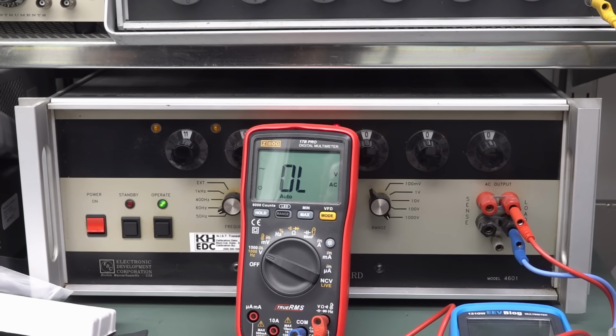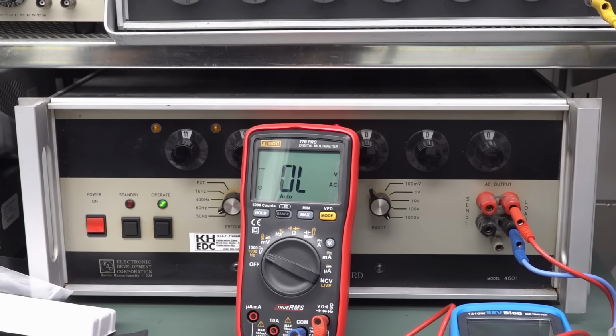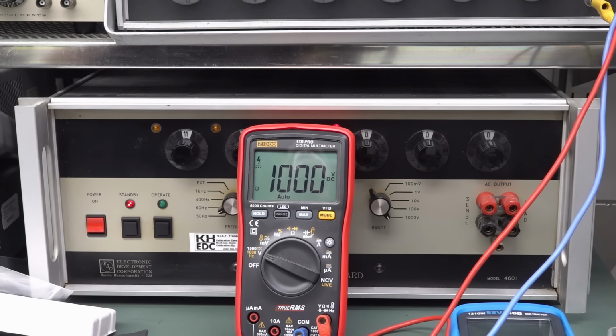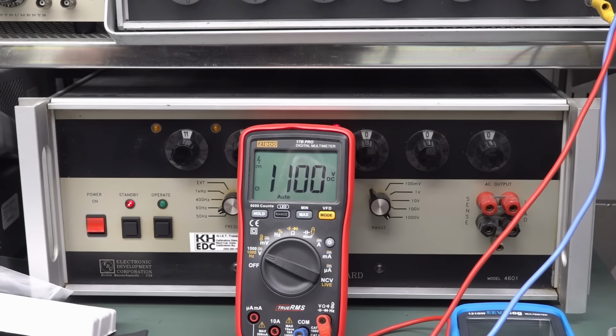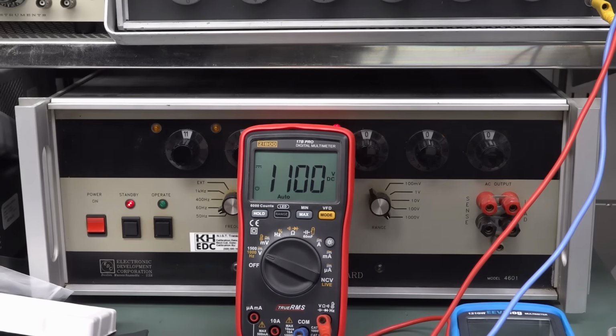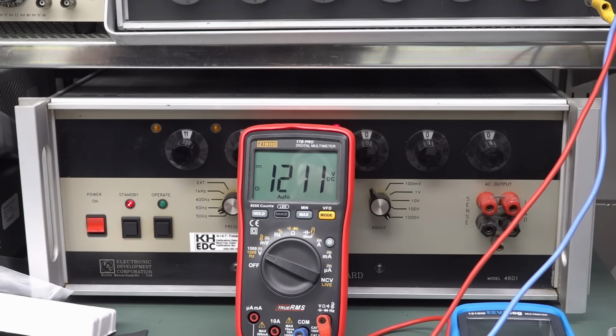What? There we go, so much for the 1500 volts. There you go, can do 1000 volts AC, but 1100, can't do 1100. Oh, and I've got it hooked up to my DC standard, and it'll measure 1000 volts. Will it measure 1100? Yes, it will measure 1100, that's as far as I can go. Well no, actually, I can go a little bit higher than that, but that's about 1200 volts. Okay, so I might get to 1500 volts DC, but it won't do it AC.